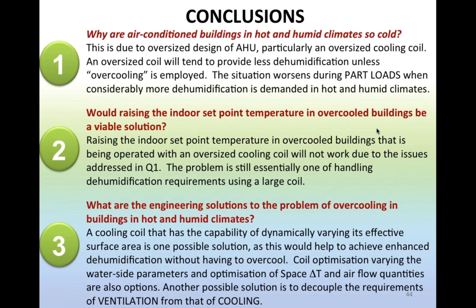Okay, I think fundamentally, from a conceptual point of view, what cooling medium is used is probably not going to be that critical, but let's translate that in terms of how systems are actually used in building designs and are available in the market. When we have refrigerant-based systems in smaller applications, that is, split system units or otherwise, with the indoor unit versus your heat rejection unit being outside, it is a great system where you move the noisy part and the heat rejection part to an outdoor environment and just have a fan coil move air around within the room.